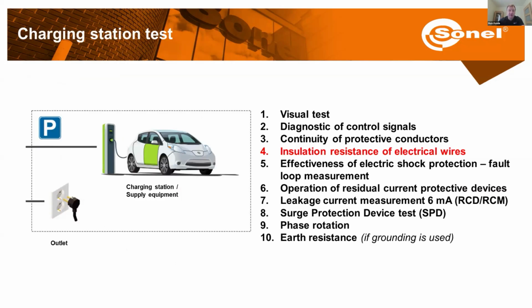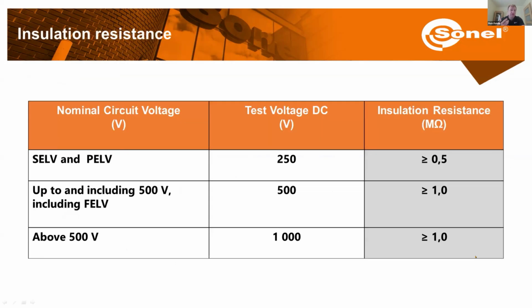Now the next test is the insulation resistance. Here we need to adjust our test voltage. We have a table from the standard, and depending on our nominal voltage, we adjust the test voltage, and we have the requirements for the minimum value of the insulation resistance. Typically, depending on the charging station, if we have voltages up to 500 volts, we test the station with 500 volts DC, and the minimum requirement for insulation resistance is above 1 megaohm. If we have charging stations with voltages above 500 volts, then we need to test them with 1000 volts DC test voltage, and the minimum requirement for insulation resistance is again 1 megaohm or higher.